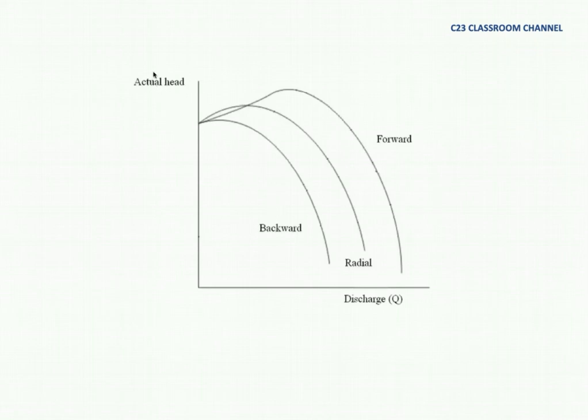This is the graph showing the actual head and discharge. This is the curve shown by the backward blade, this is radial, and this is forward. In reality, the actual head will have this kind of curve. When the pump has backward blade, if we increase the discharge, the actual head will decrease. The radial will slightly decrease and then decrease like this. The forward will give a long range of increment in actual head before it goes down like this.